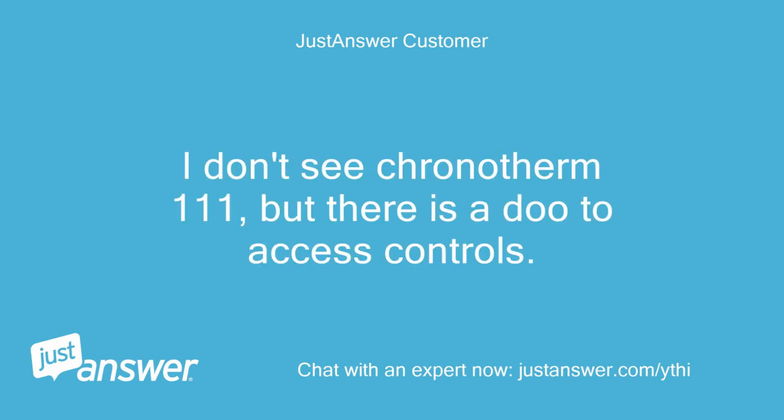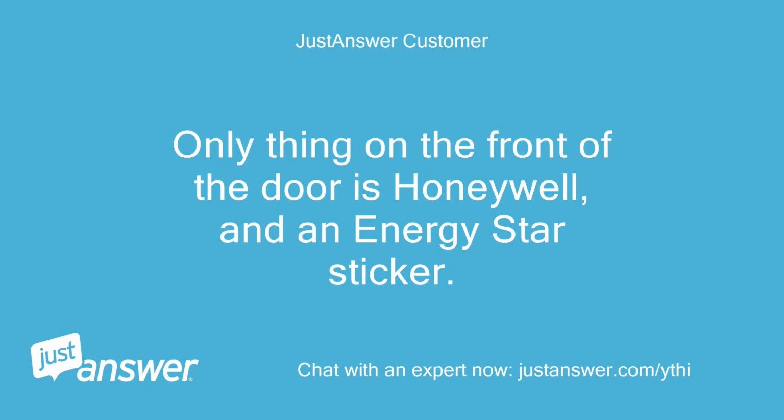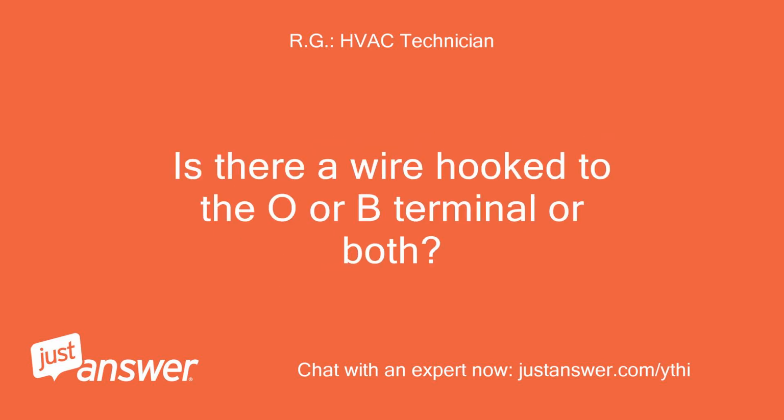I don't see Chronotherm 111, but there is a door to access controls. Only thing on the front of the door is Honeywell, and an Energy Star sticker. Okay, R is 24 volts to stat, but if it wasn't making contact, unit shouldn't keep running. Is there a wire hooked to the O or B terminal or both?